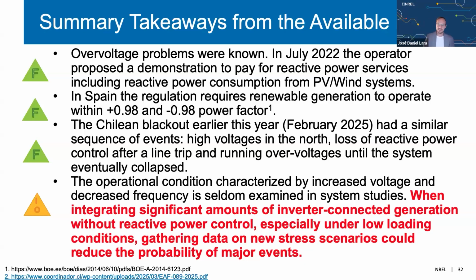Now, integrating significant amounts of inverter-based generation that doesn't provide reactive power control under low loading conditions means we have to rethink which scenarios we study in integration analysis, and whether gathering new data about these stress scenarios could reduce the probability of major events.